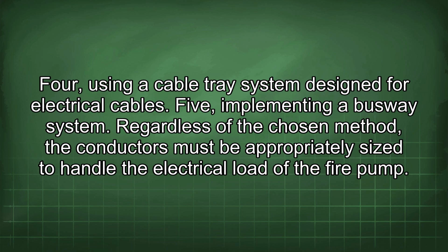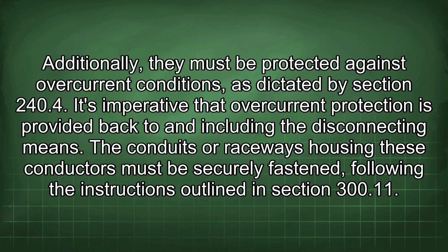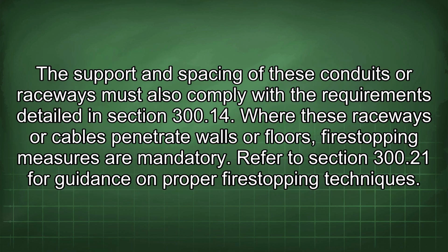Regardless of the chosen method, the conductors must be appropriately sized to handle the electrical load of the fire pump. Additionally, they must be protected against overcurrent conditions as dictated by section 240.4. It's imperative that overcurrent protection is provided back to and including the disconnecting means. The conduits or raceways housing these conductors must be securely fastened following the instructions outlined in section 300.11. The support and spacing of these conduits or raceways must also comply with the requirements detailed in section 300.14.